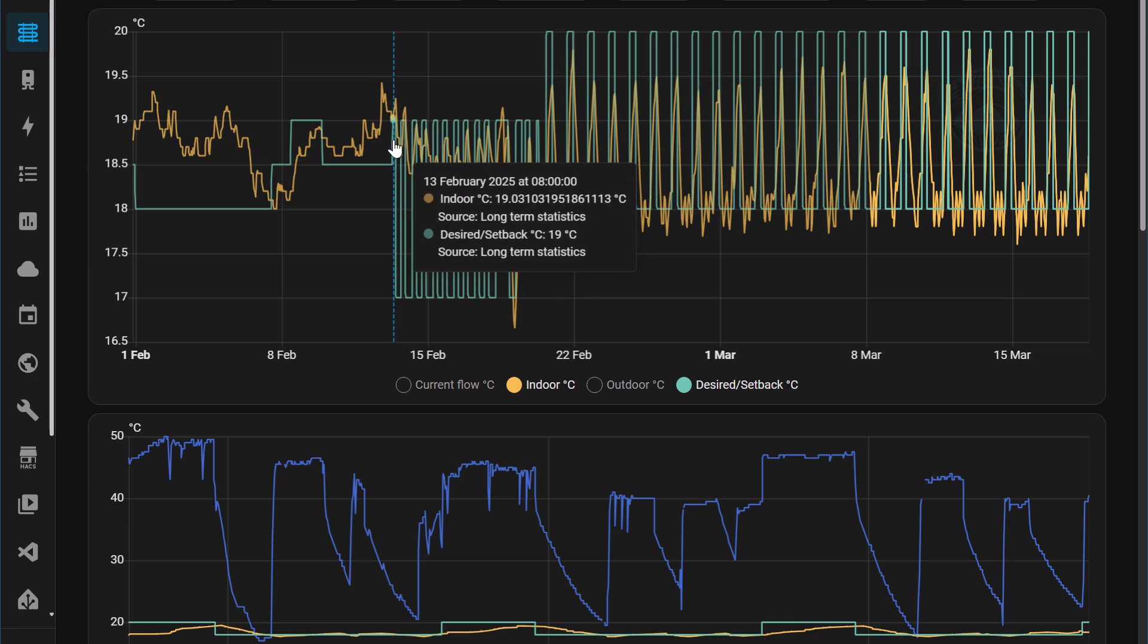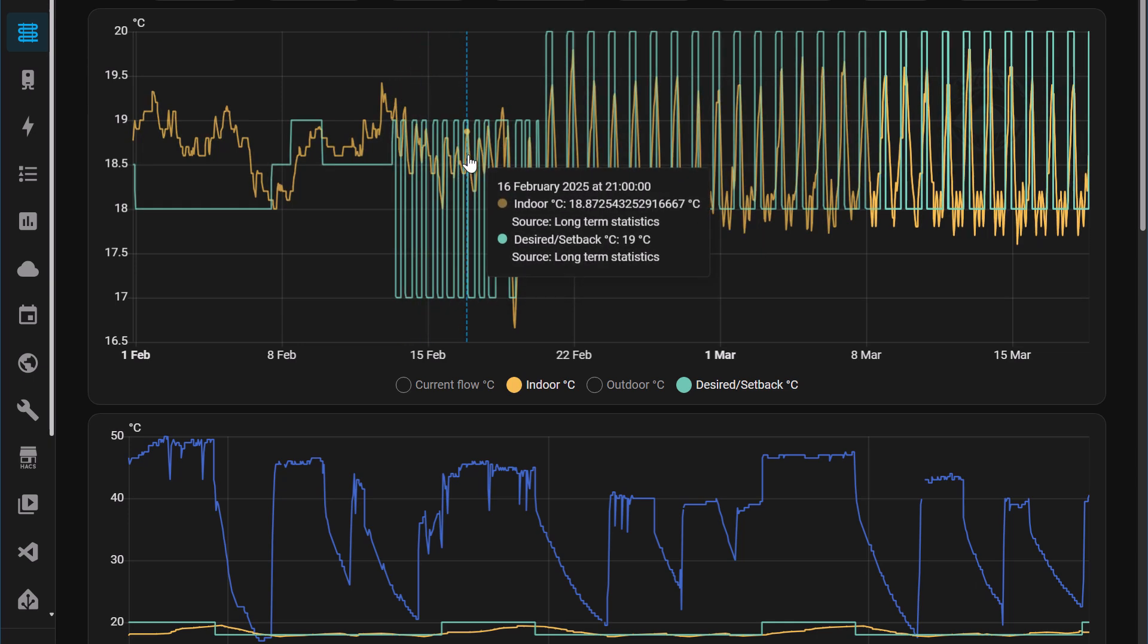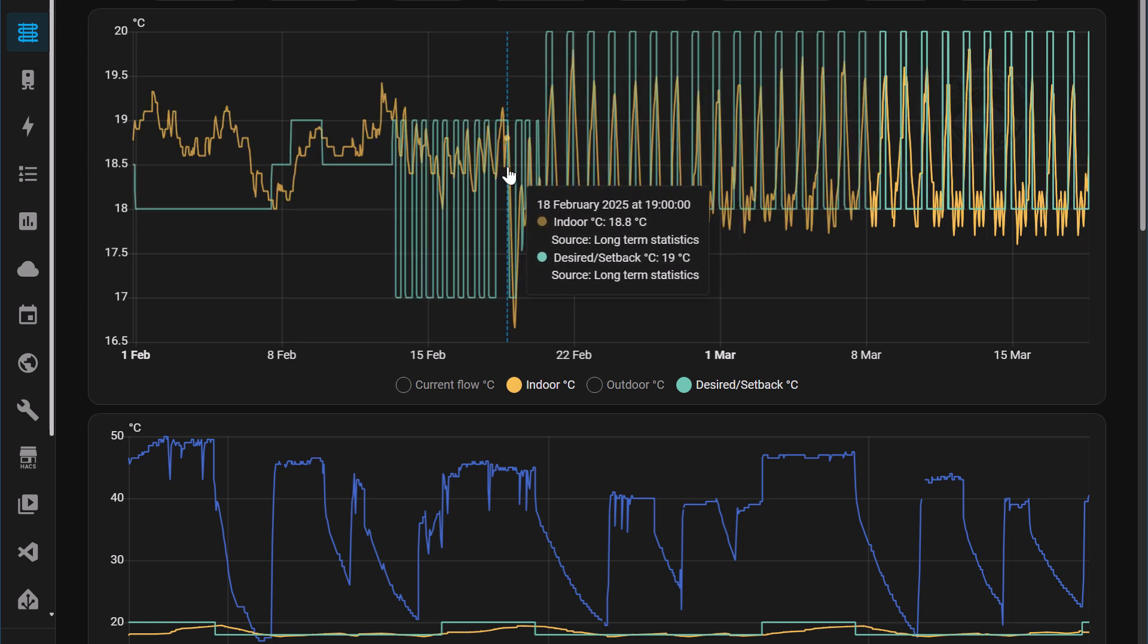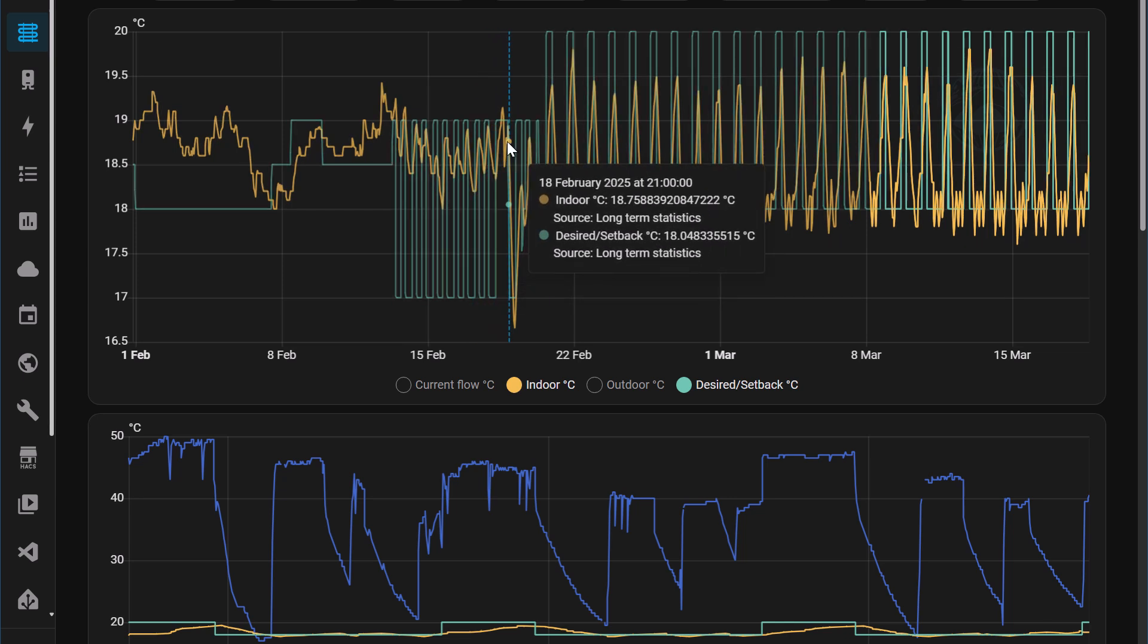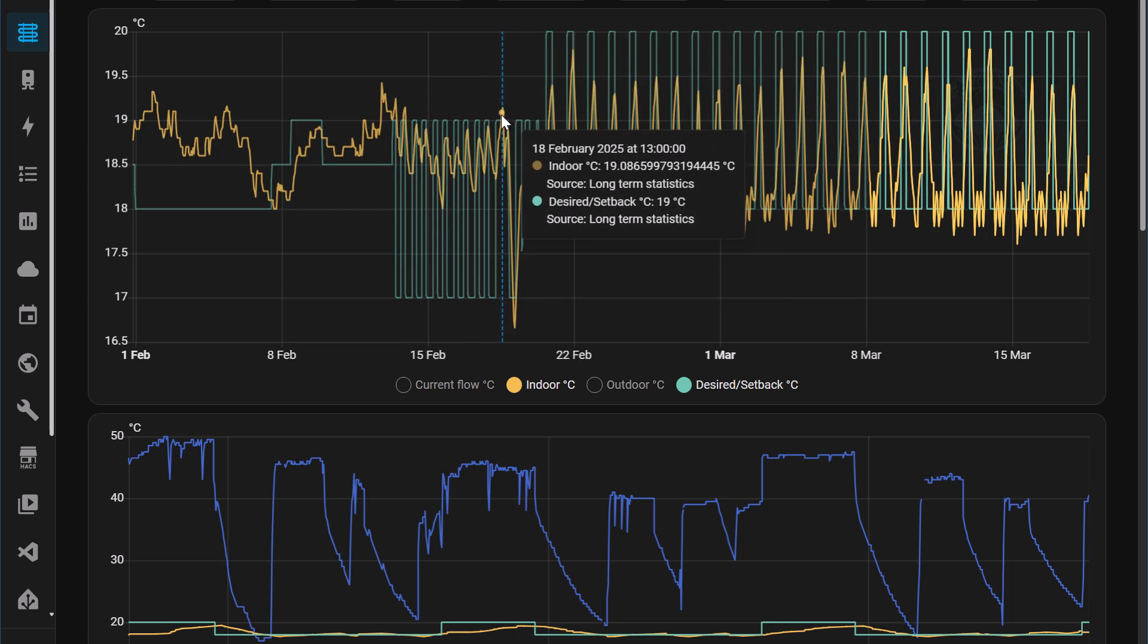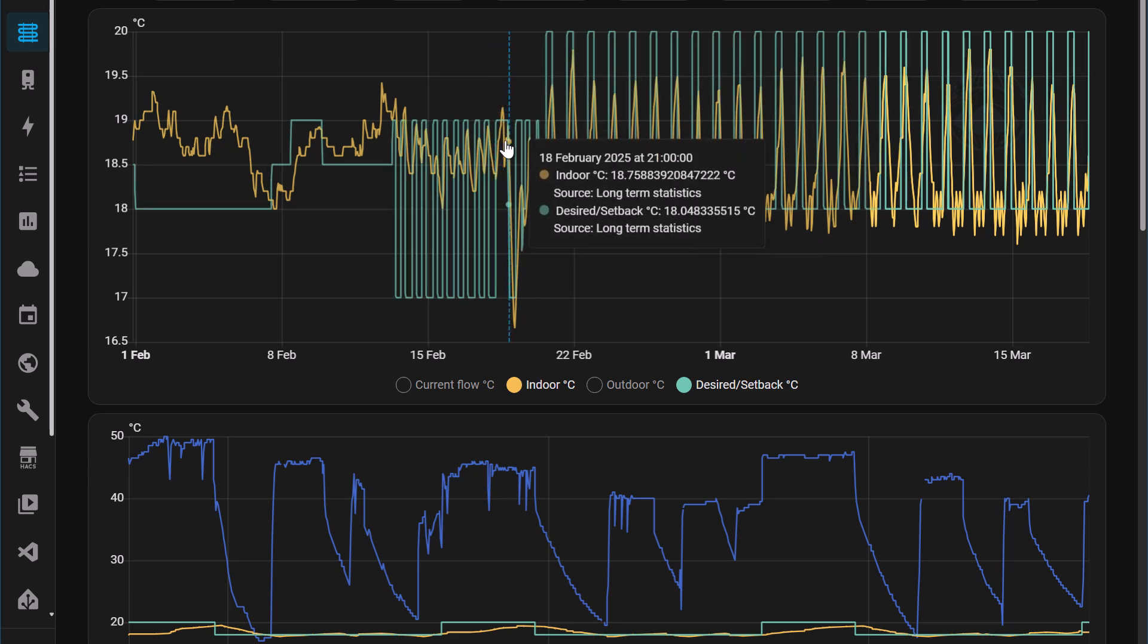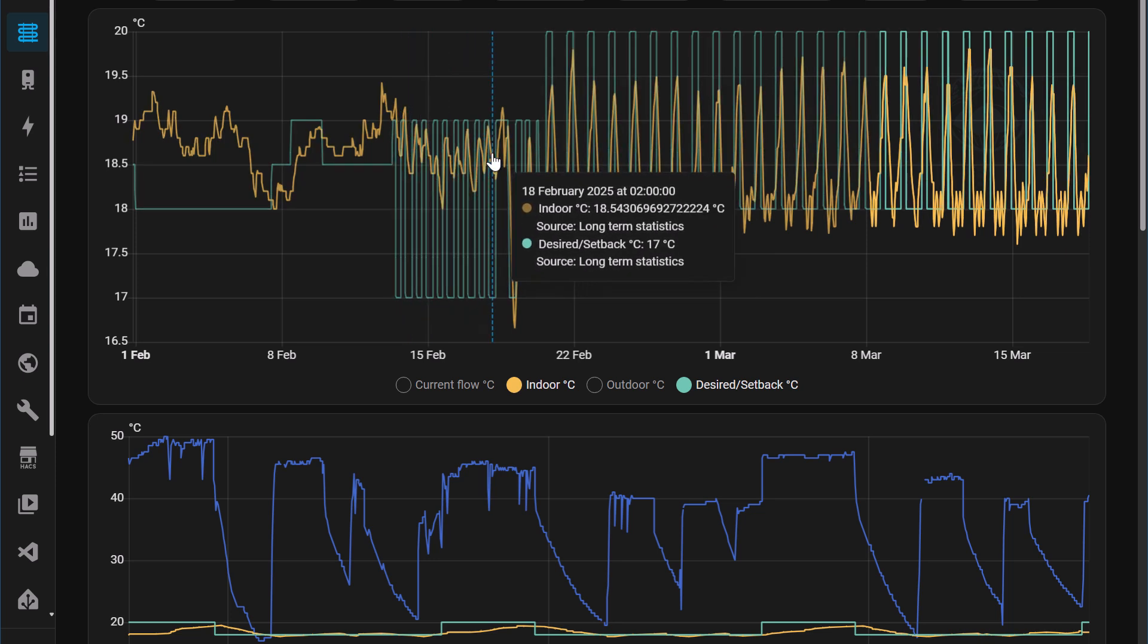You'll also see that the indoor temperature never really hits the desired temperature. Places where it has hit the desired temperature is a result of bumping up the heat curve from maybe 1.3 to 1.5. Now that clearly was too much and this is why the indoor temperature went through the desired temperature. But all through the previous days it never really reached that.